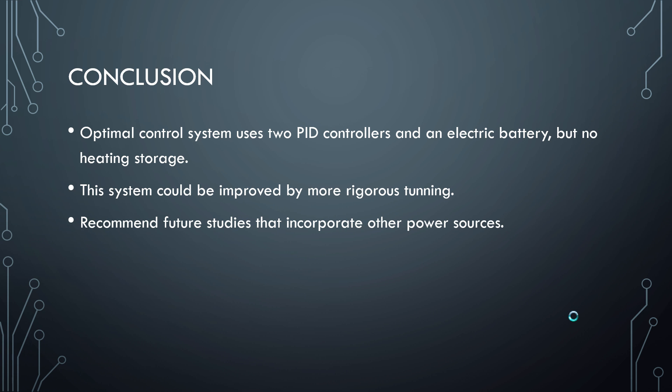In conclusion, the optimal system included two PID controllers that would switch depending on which had the maximum output, to keep it from going into a negative range. It was also optimal to have one electrical battery and no heat storage device. Going forward, we'd recommend more rigorous tuning, further analysis incorporating natural gas as an additional power source since it can change output with less damage to the system, and also testing with solar power, as it is also an intermittent source.